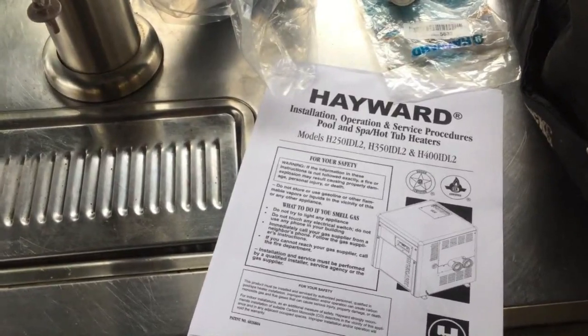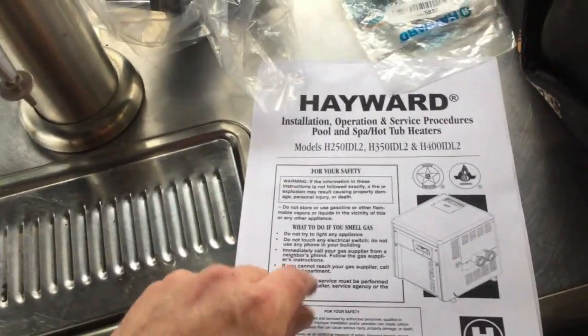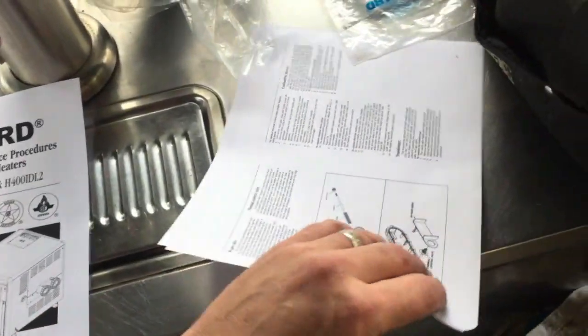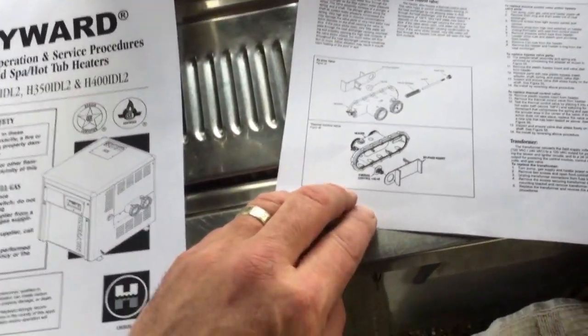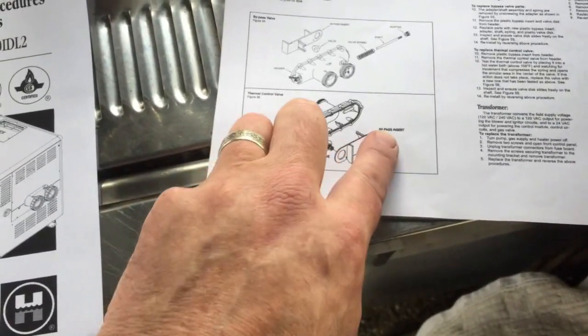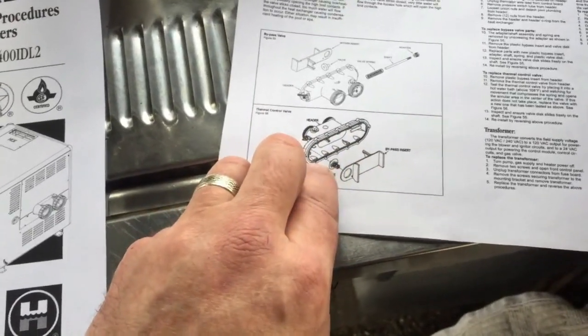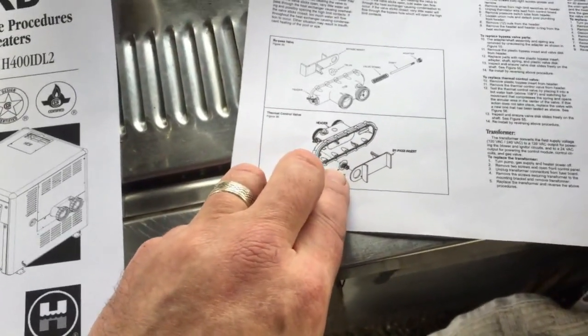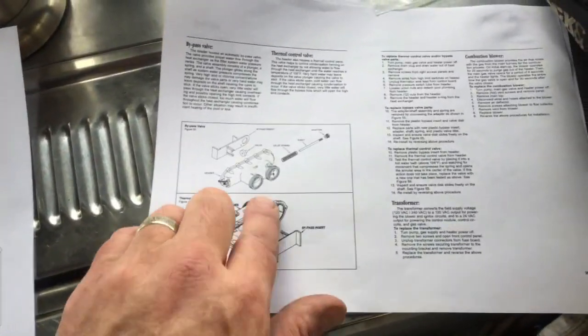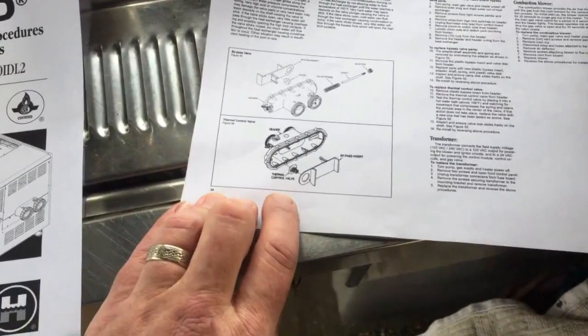I looked around and found that there are actually two components — and by the way this is a Hayward model H400IDL2 that we'll be working on today. Looking through the manual, I found the two things that control the heat are right in here: this thermal control valve and this bypass insert plate. The two kind of completely block the flow or let it bypass around. I pulled this unit off and found that actually both of them were pretty badly damaged, which I'll be showing you.